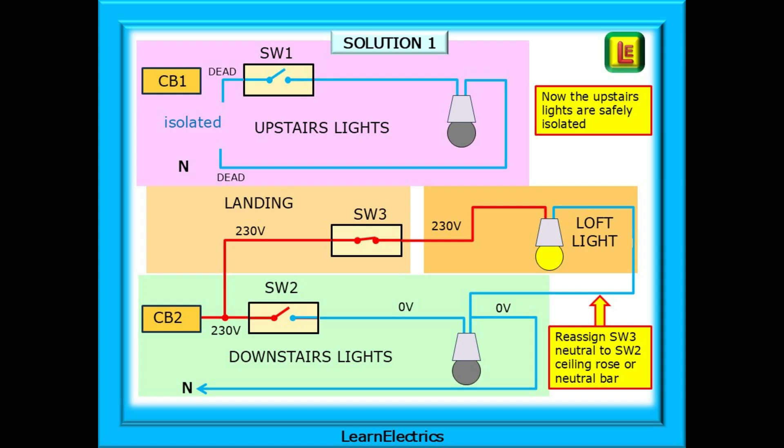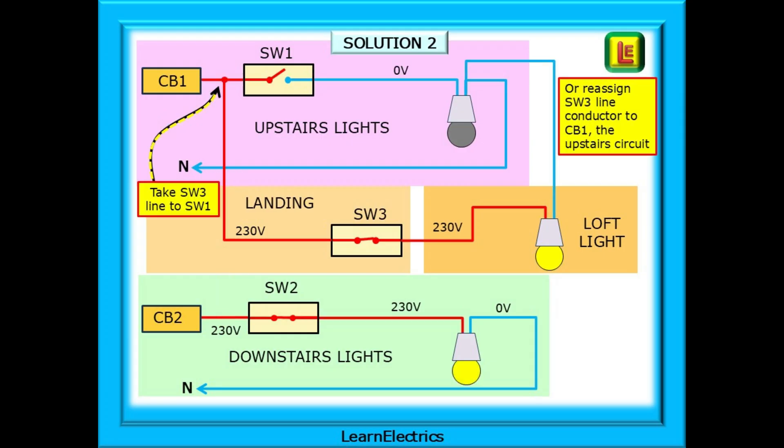There are a couple of solutions to this problem. Two ways of making the installation safe. Reassign SW3 neutral to SW2 ceiling rose or to the neutral bar. Now SW3 belongs entirely to circuit breaker number 2 and the upstairs lights can be safely isolated. Whatever happens with the loft light is not going to affect the upstairs lighting circuits.